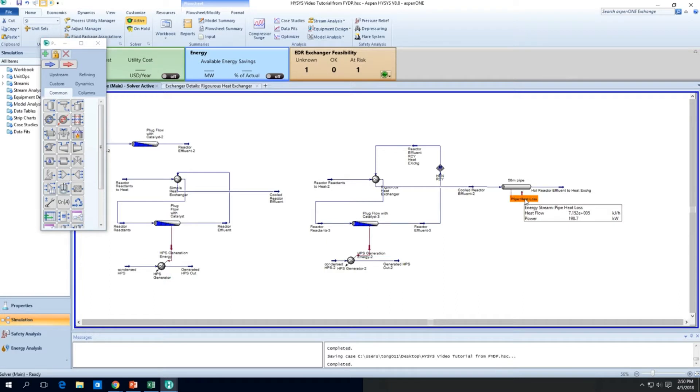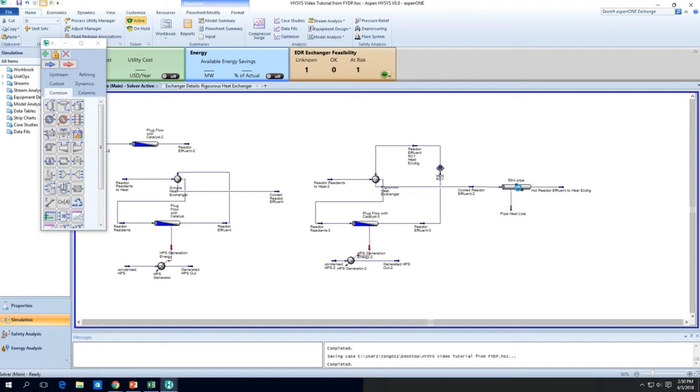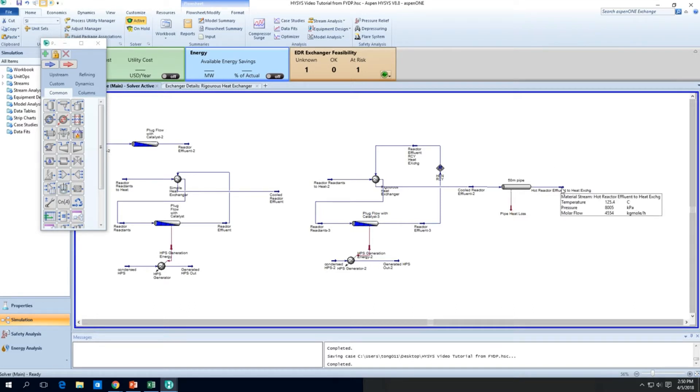I'm guessing it's at 50 watts per meter square per degree C. So that's basically it for pipe. So the pipe heat loss, I'm just going to press it a few times to get the correct heat loss value. So this is a 50 meter pipe of about 200 mm in diameter. Pressure drop about 20 kPa. Not too bad. So that's basically a pipe.